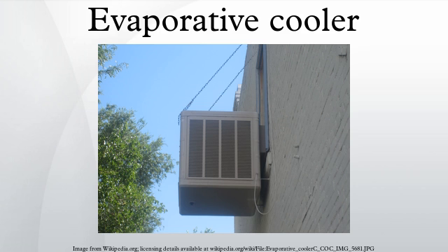Mosquitoes. An evaporative cooler is a common place for mosquito breeding. Various authorities consider a poorly maintained cooler to be a big threat to public health. Miscellaneous. Evaporative cooling towers are the most common sources of Legionella and Legionnaire's disease. Odors and other outdoor contaminants may be blown into the building unless sufficient filtering is in place. Mold and bacteria may be dispersed into interior air from poorly maintained or defective systems, causing sick building syndrome. Asthma patients may need to avoid poorly maintained evaporatively cooled environments.